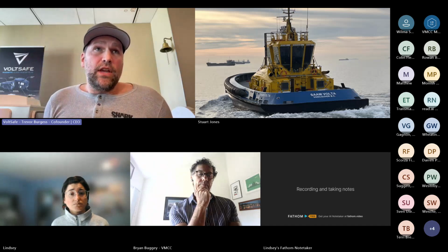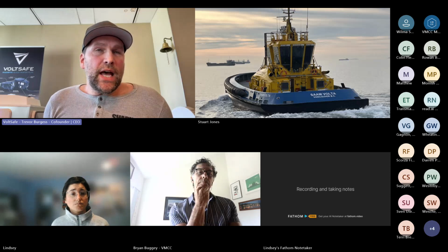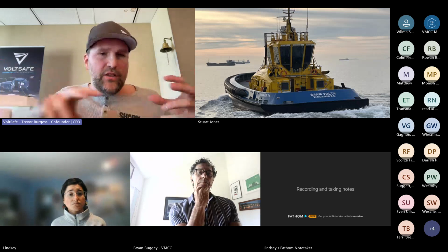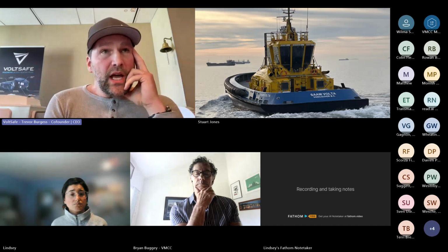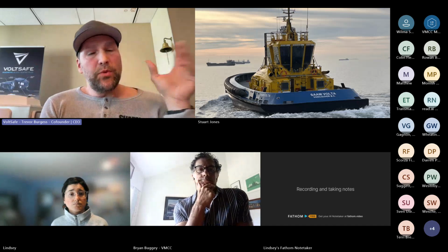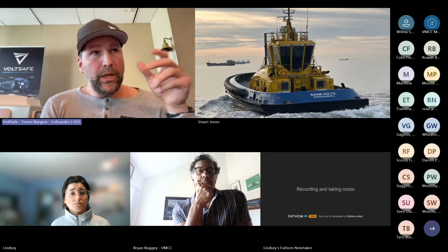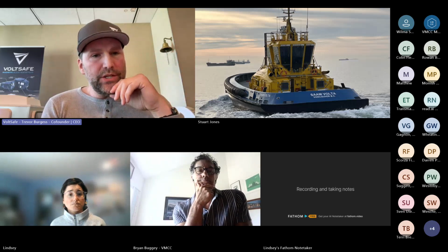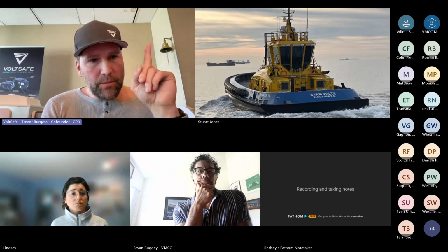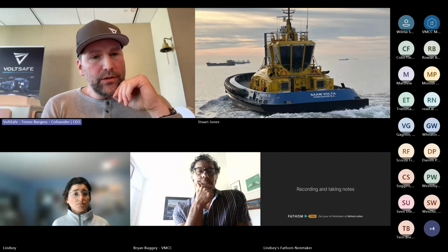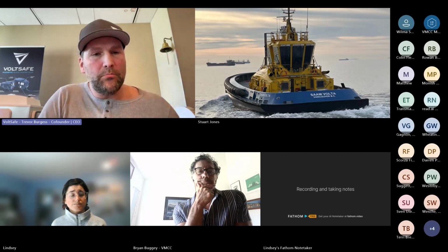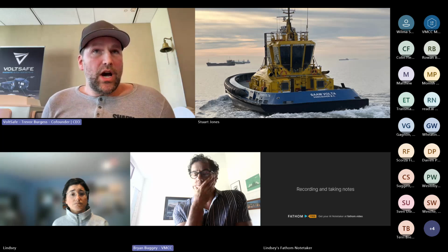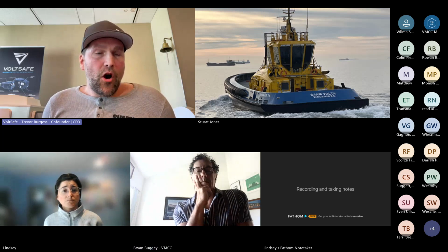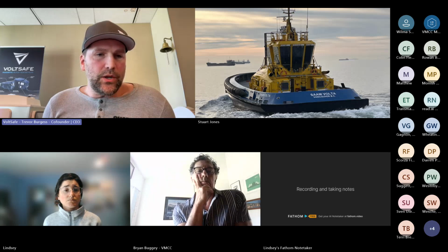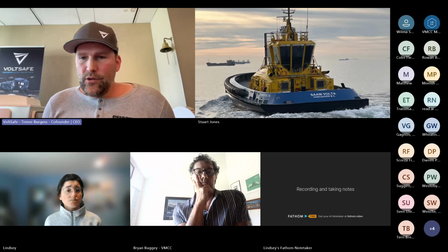For Canada, they do the same thing but allow marinas to install it at the sub panel, covering a whole chain on the whole dock. But the reason they're going to change that to each slip is because putting it on the sub panel makes it completely unusable - in a lot of states I'd find that more than 50% of boats at one slip would trip 30 milliamps. So you've got this systemic problem of older boats with current leakage at a level already past what NEC just instituted. This is critical and key.